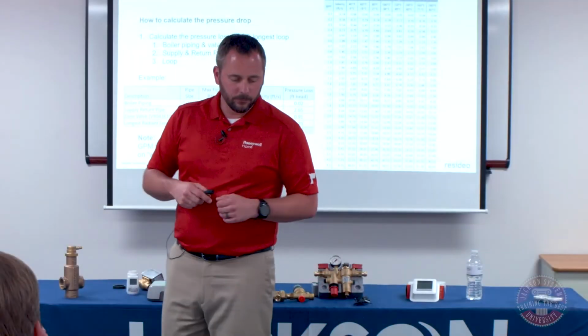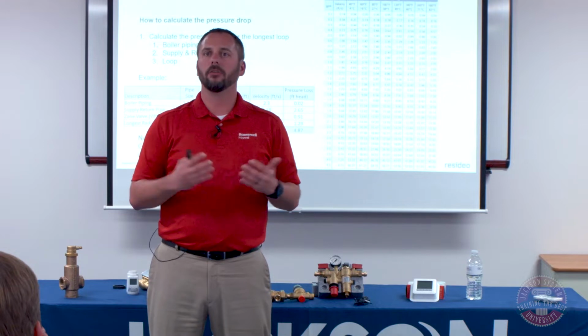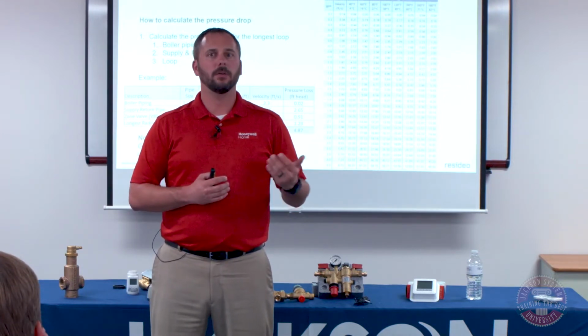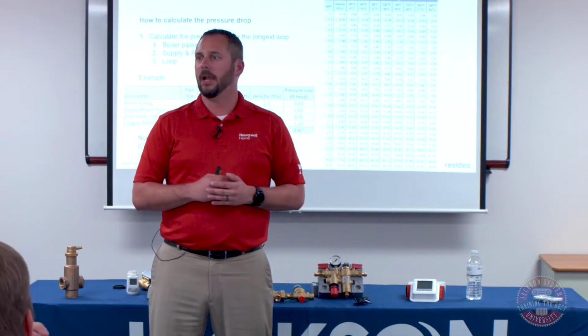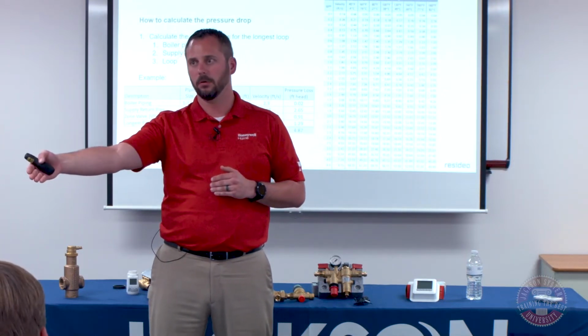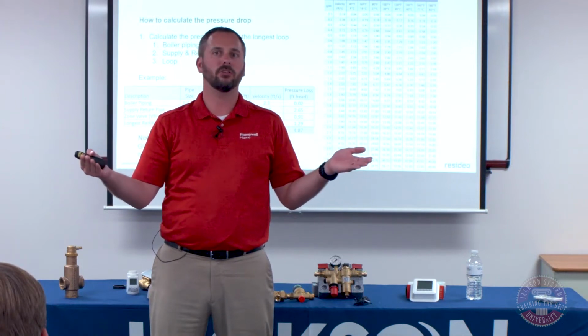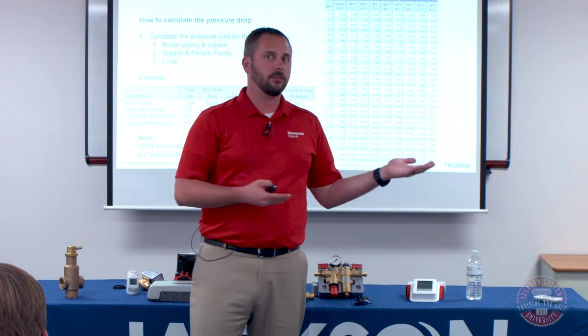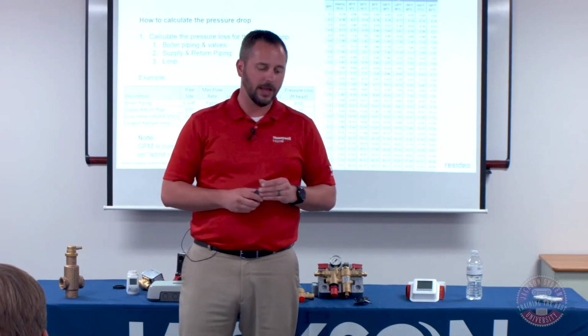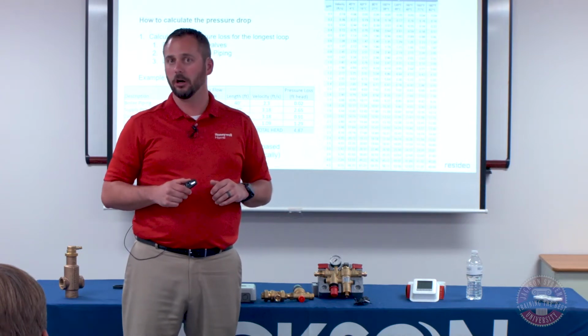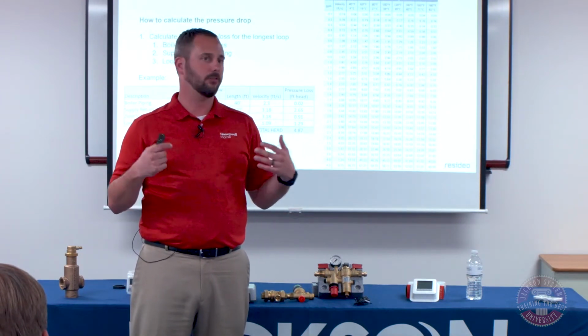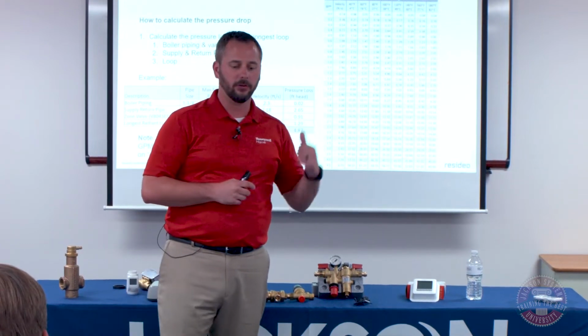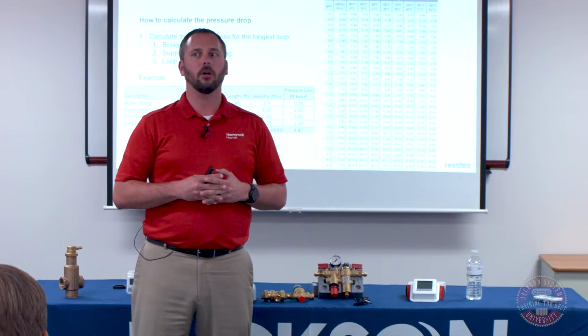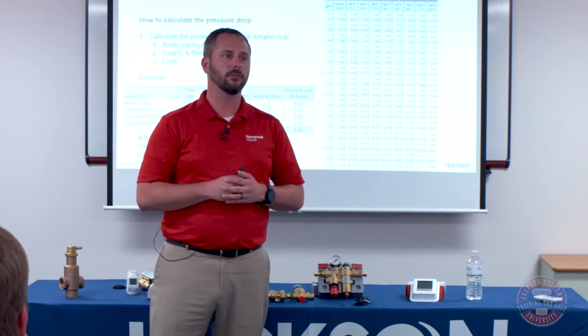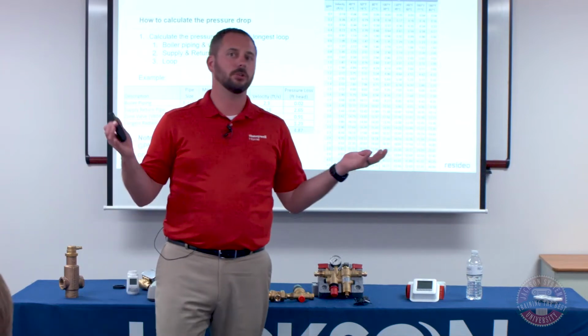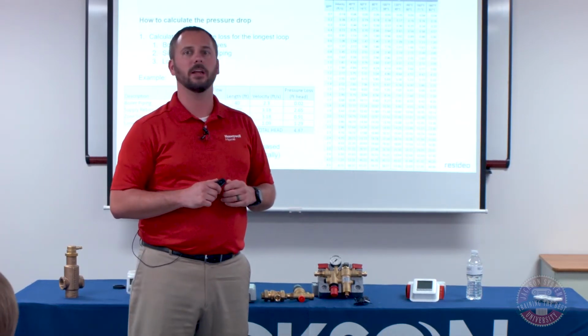So in order to do that, what I usually do is go through and break out where the water is traveling from and to. So I'm leaving the boiler. I've got to get through the boiler piping. I've got to get through the supply and return piping to that manifold. And then we could have 4 loops on that manifold, so which of those 4 loops is going to be the longest? That's the quickest and easiest way to do it. So I've got an example down here, and you can come up with pressure loss charts all over the place. There's an engineering toolbox on the internet that has pressure loss at varying flow rates. Uponor, a big PEX manufacturer, has got all their pressure charts listed. And I've got an example here on the right for half-inch PEX, because that's probably the most common when we're looking at in-floor heating systems.